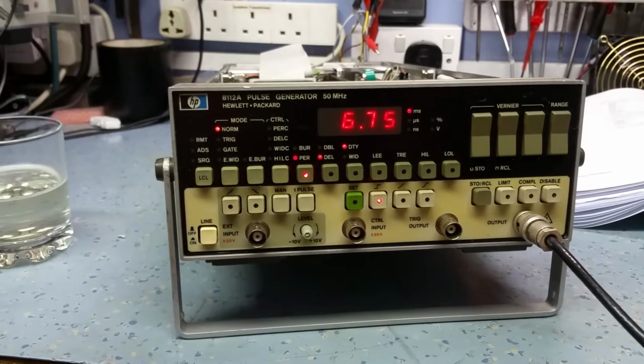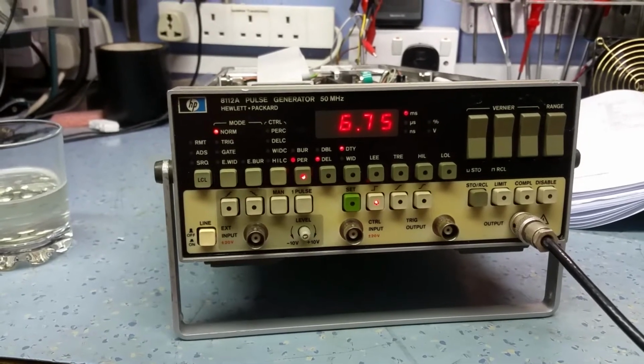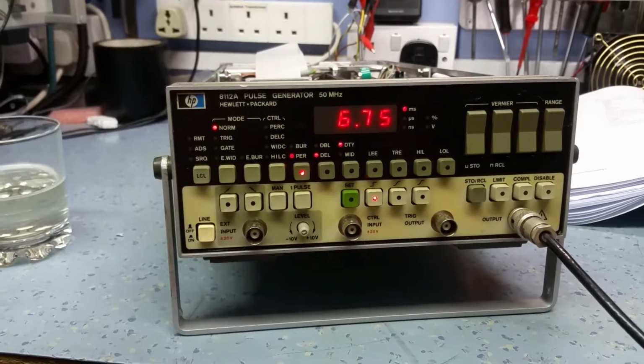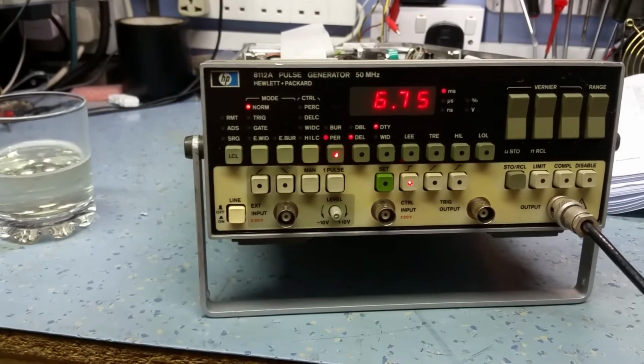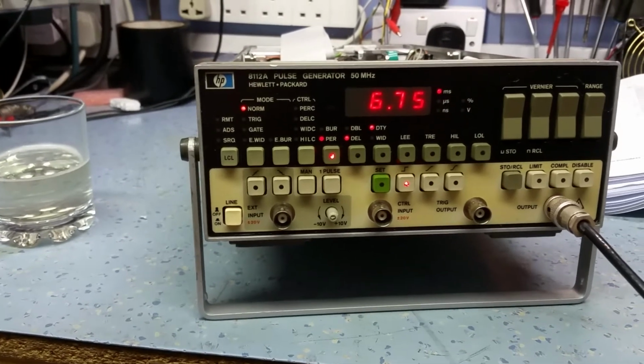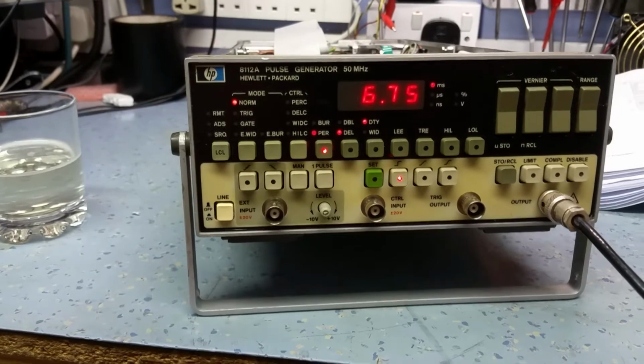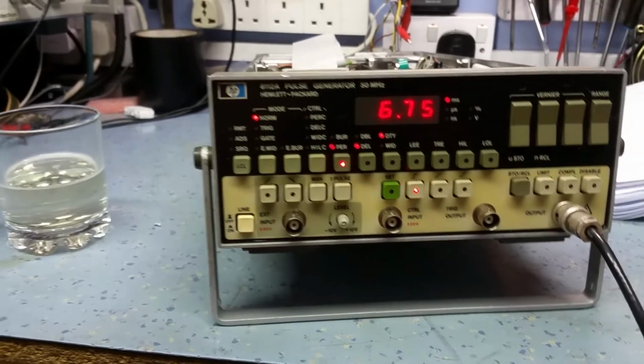This unit, to me, looks like it's never been calibrated since it left the Hewlett Packard factory back in the 80s. It was quite a way out on its pulse width and its period times. So I've run through the calibration, and it's fairly straightforward. The manuals are available online.